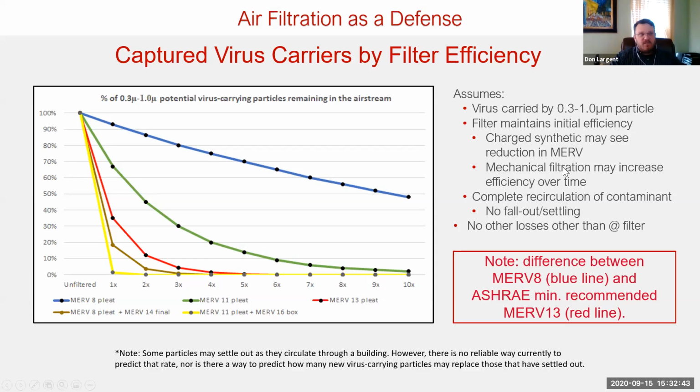And in that case, typically your mechanical filtration will increase over time as the filter loads, it becomes more efficient. However, the pressure drop also will rise as well. Again, the assumptions here were that the viral load would continue to recirculate continuously and no fallout, no other losses.